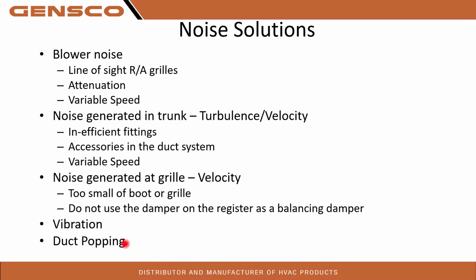Duct popping, that's a big one, right? So if it's undersized, that's what the cross break is in there for. You'll hear that return air suck in, it'll shut off, it'll pop back out. So that is a crazy noise if it's loud and in the middle of the home. We want to be aware we might have some static pressure issues for undersized ductwork.